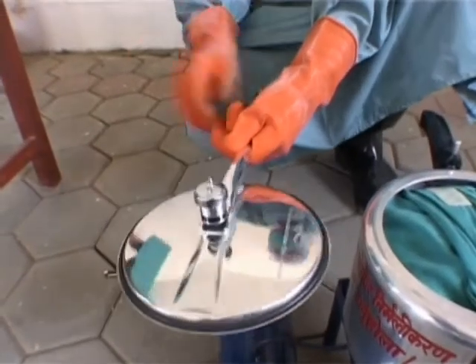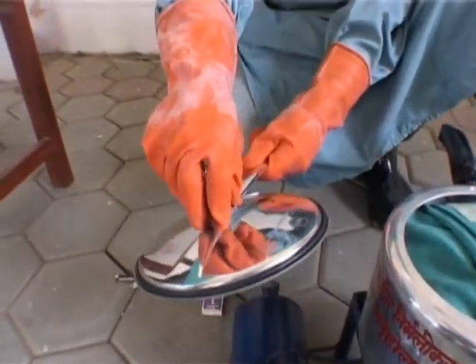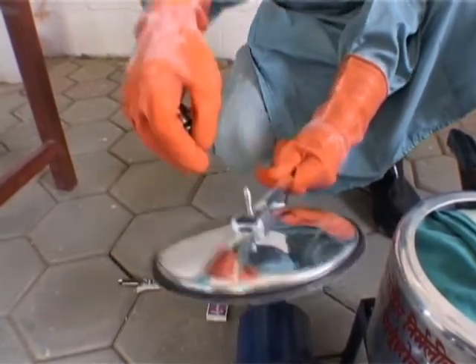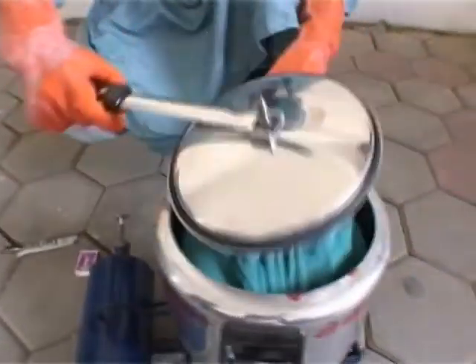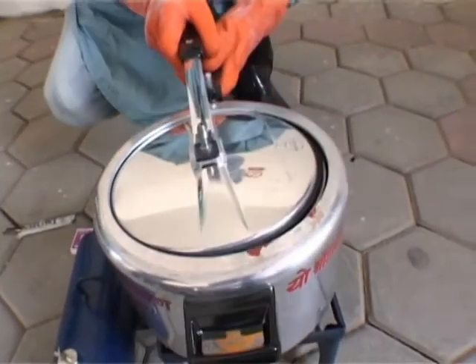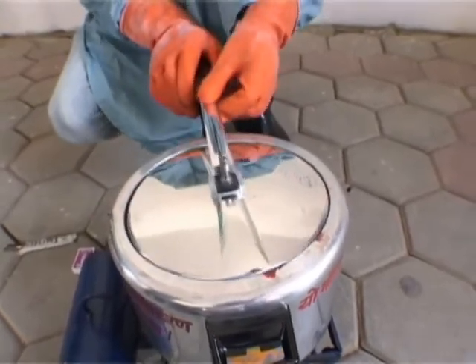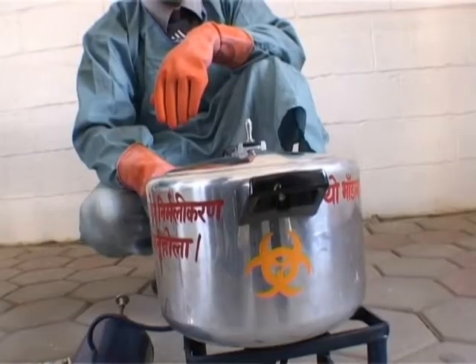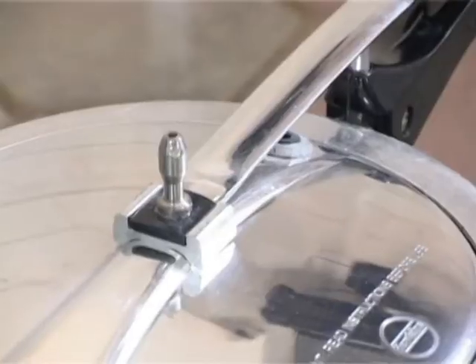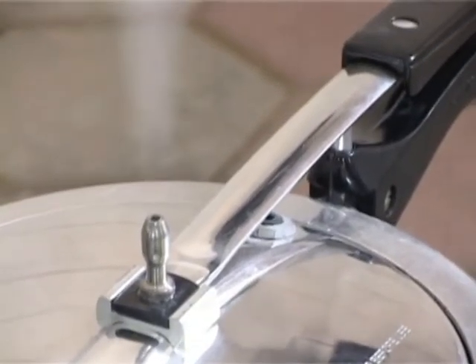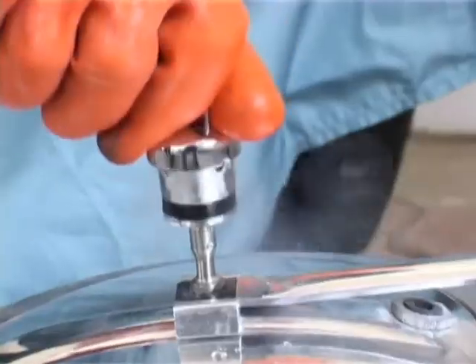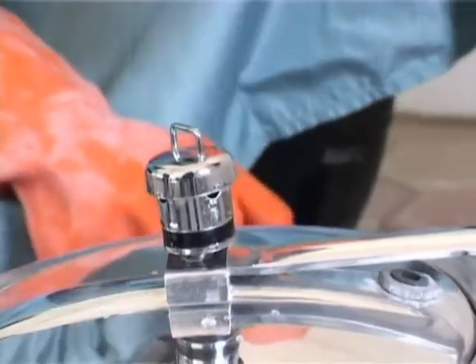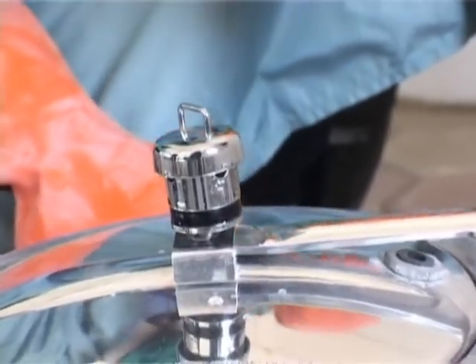Step 6 is to remove the regulator valve. Before closing the pressure cooker lid, the regulator steam release valve must be removed. With the regulator valve removed, place and properly seal the lid on the pressure cooker. Wait for steam to visibly exit from the nozzle. Once this occurs, you can be certain that you have reached the proper temperature for sterilization and the regulator valve can now be replaced.